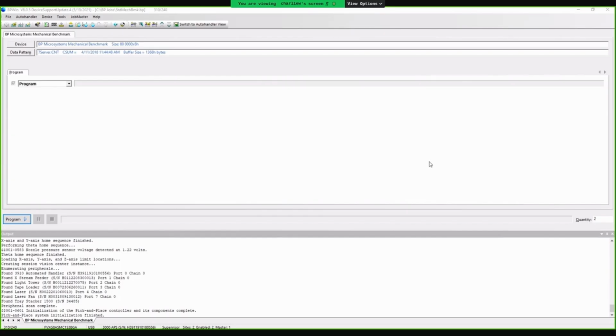Sure. So yeah, laser marking, of course, is going to be burning the surface of the device, which creates dust. And of course, we have a robust dust collection system inside the machine, a HEPA filter, and also a carbon charcoal filter. And those need to be serviced on a regular basis. And that's part of the machine maintenance. And there's a shutter, of course, that we can operate safely, a safety shutter. That's right. So everything is enclosed.